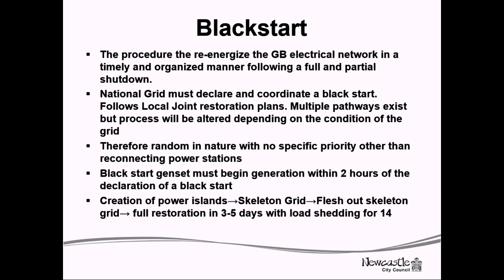You need a black start genset, and that has to happen within 2 hours. On our current planning assumption, to get a full restoration of the UK electrical grid after a black start scenario, you're looking at 3 to 5 days, with the potential for 14 days of load shedding. Load shedding is where you power someone, then because you don't have enough power for everyone, you take that power away and give it to someone else. It happens in some electrical systems around the world where supply isn't reliable, but it would be controlled. The 3 to 5 days is also an extension - it used to be 24 hours to 3 days, and now it's up to 5 days, so the actual window for full restoration has increased.